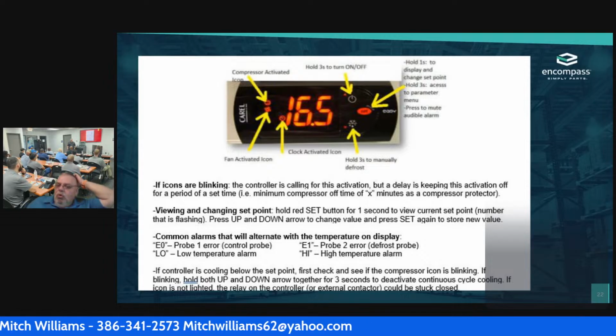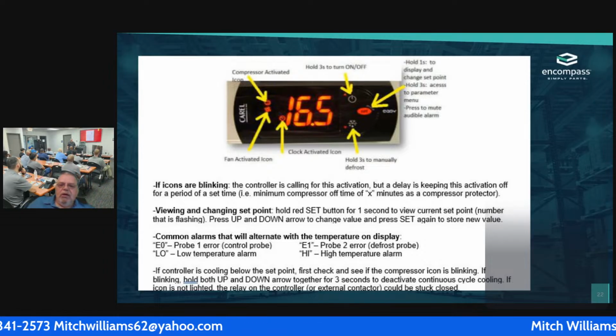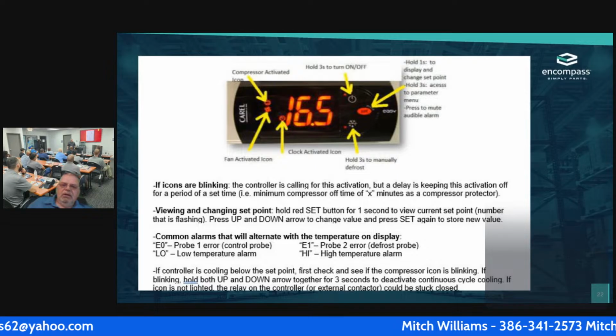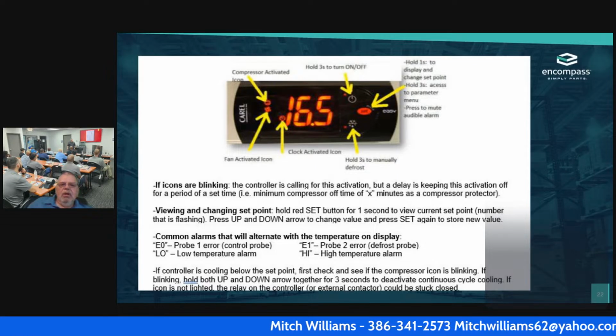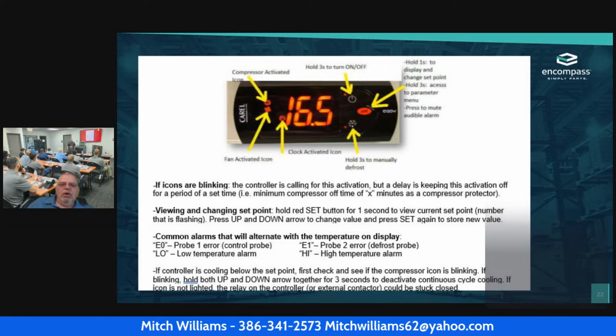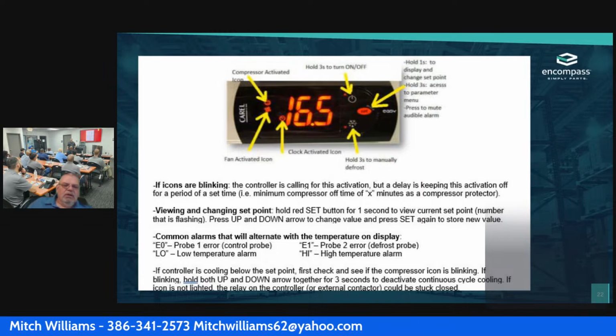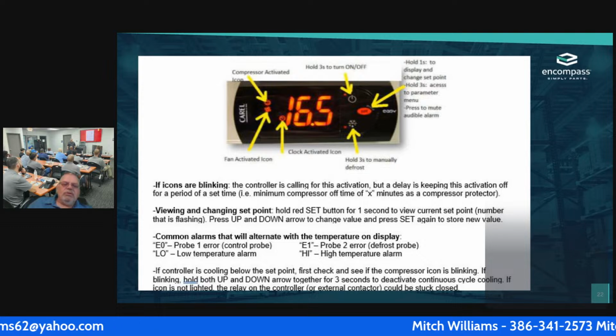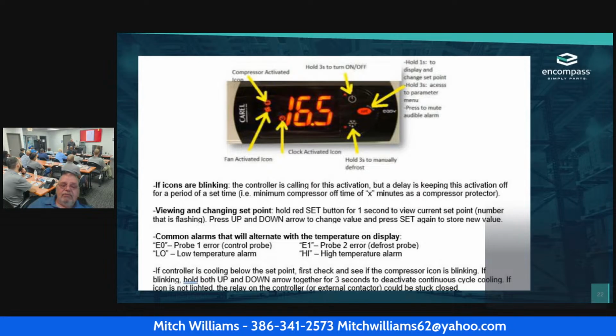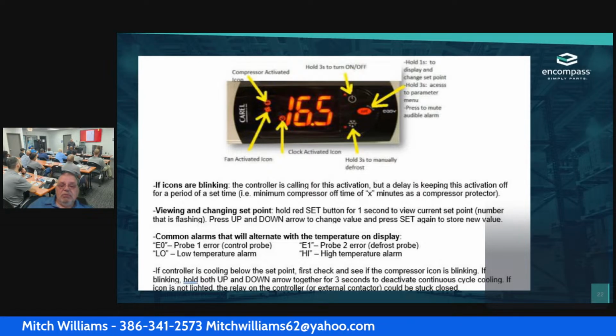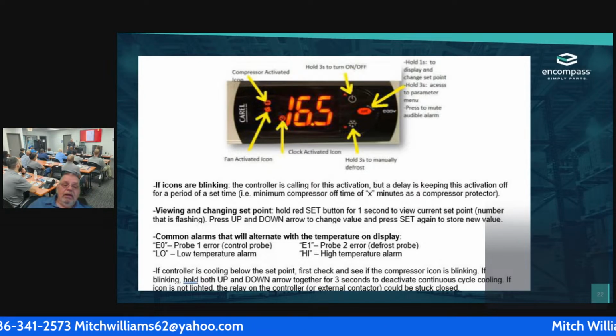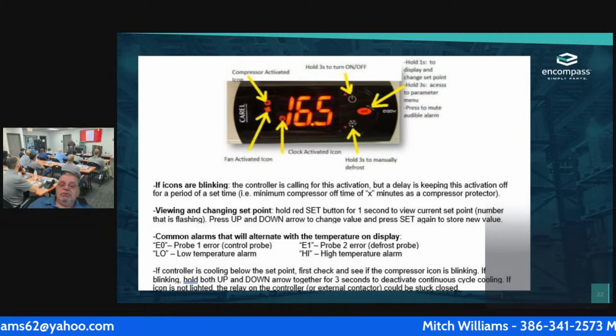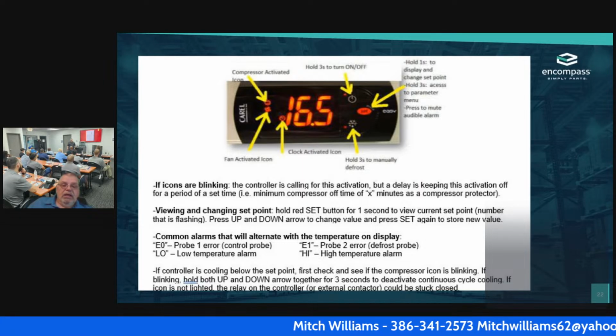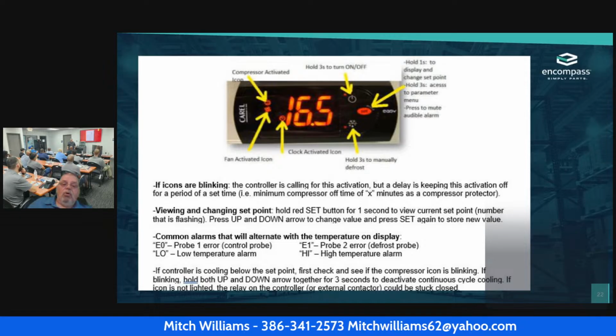If I have an E1, that's the probe 2 error, and that's the defrost probe. The ones that I've seen, the E1 is the one that goes out first, and that's the defrost probe. If we have an LO, that's a low temperature alarm. That means that it's gotten lower than it should have. If I have a high, that tells me that I have a high temperature alarm. And once again, I'm going to have to check those probes. So I usually will get an E0 followed by an LO or an HI.